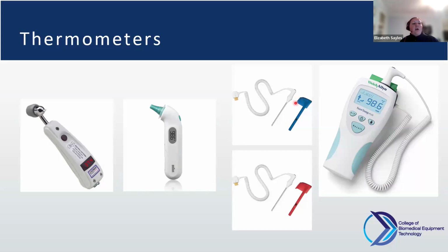So the blue can be used for oral or axillary. They specifically color code rectal thermometer probes, the probe well red, so that you're not using the same probe taking an oral temperature for a rectal temperature. There are covers that go over these probes because of multiple patient use, and so the probe covers go over it. But they want to make sure that you're aware that this thermometer is being used for rectal temperatures, because even though there's a probe cover, and they should be cleaning the thermometer after every use, at the top of the probe here there's always the possibility that they're not getting it exactly as clean as needed. So that's why there's the two different colors.